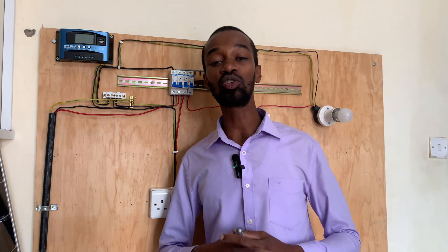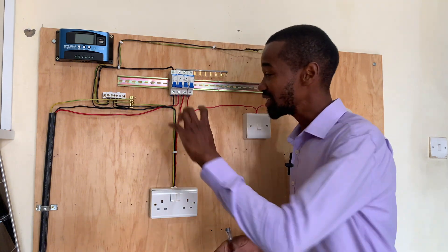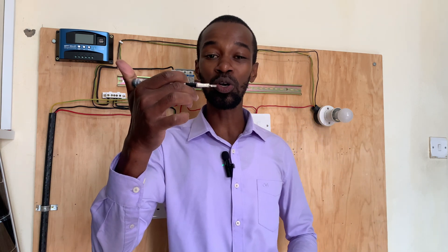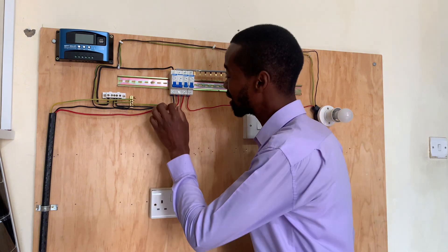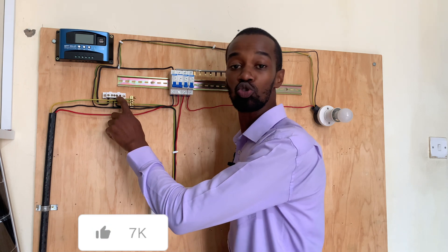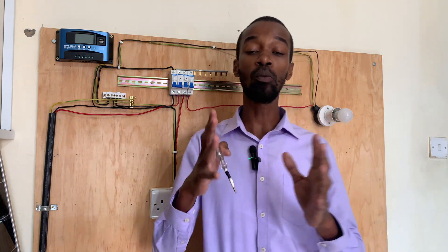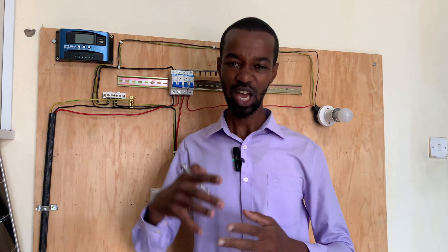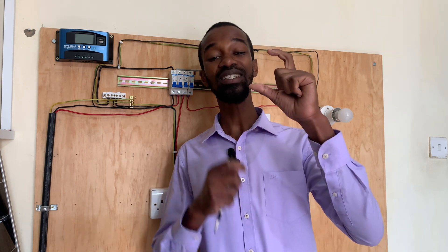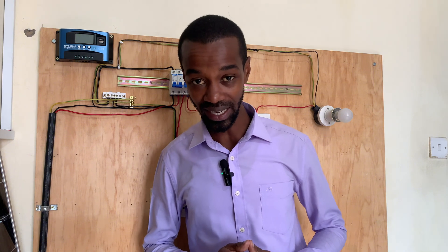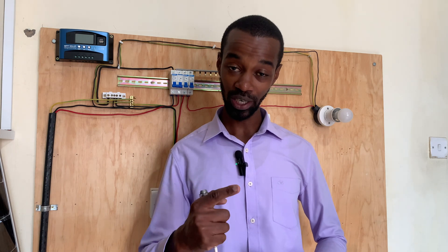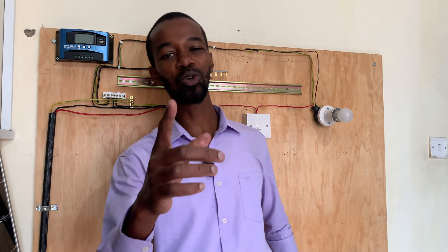A neutral line in any electrical installation is a return path to the source — the source being the transformer. In the event that there is current presence in the neutral line, it simply indicates that there is a loose connection in that entire circuit, be it on the main switch or where you have the neutral bar connecting that particular circuit. In case it is outside the consumer unit, it means it might be in the meter box, the drop cable, or at the point where the drop cable is in contact with the national grid. All of these occurrences may lead to what we refer to as a loose connection on the return path or on the neutral, leading to a floating neutral.